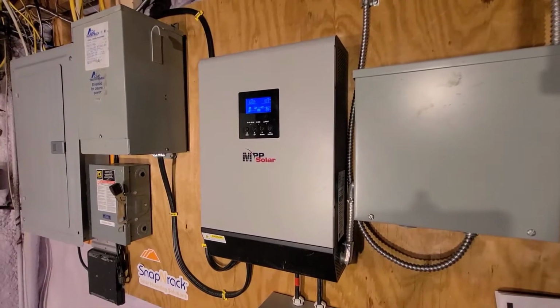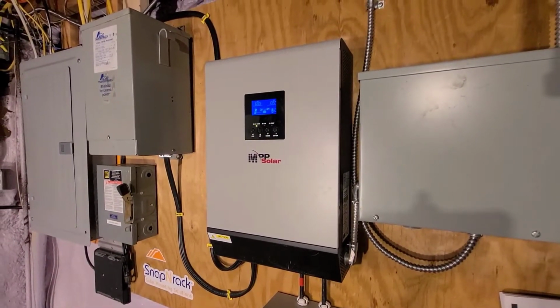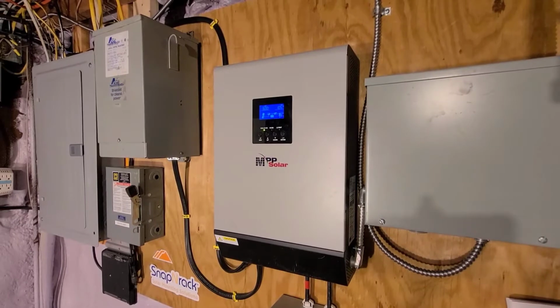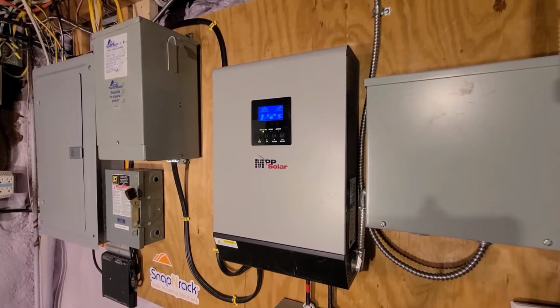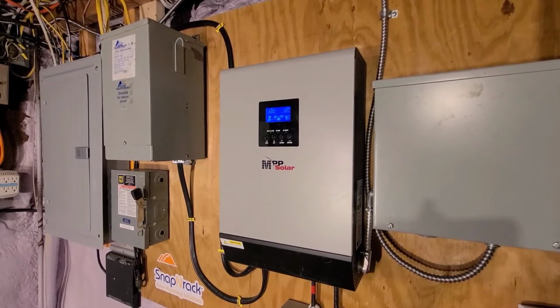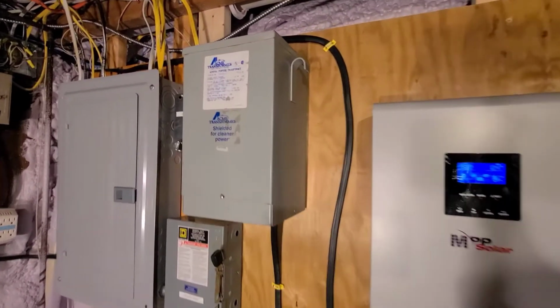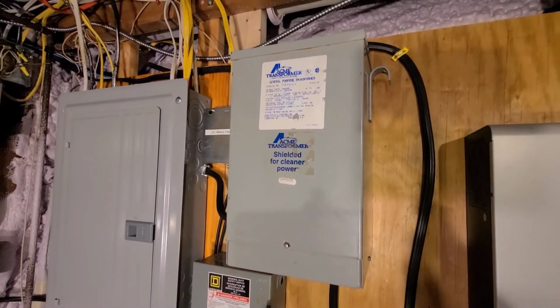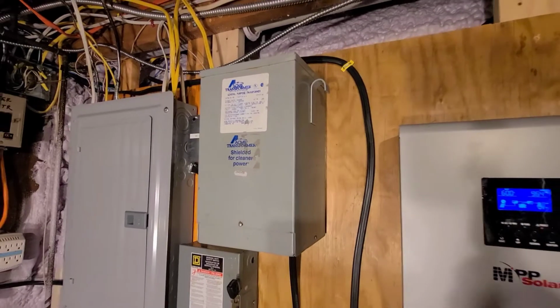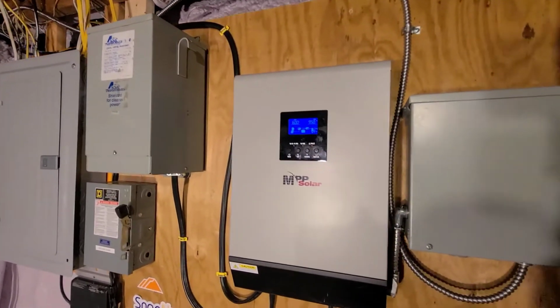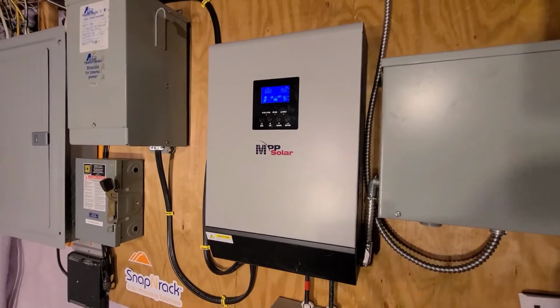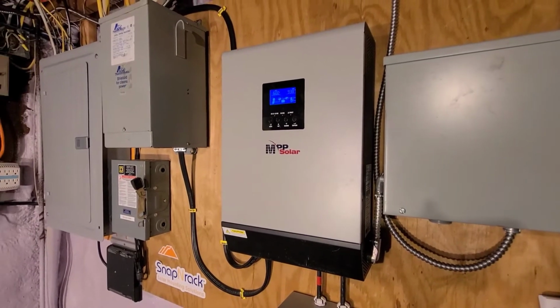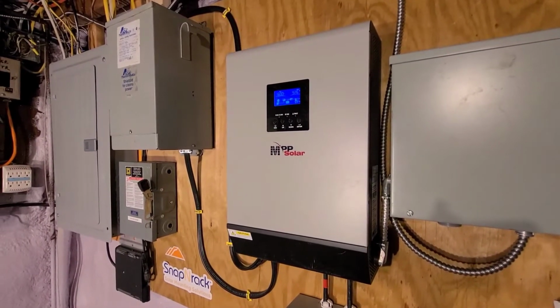So I bought this inverter in November of 2018 to use with my lithium batteries. I also got this transformer, an Acme transformer. It's a 5 kVA isolation transformer, and what it does is take the 240 volt output of the PIP and turn it into split phase 120/240.